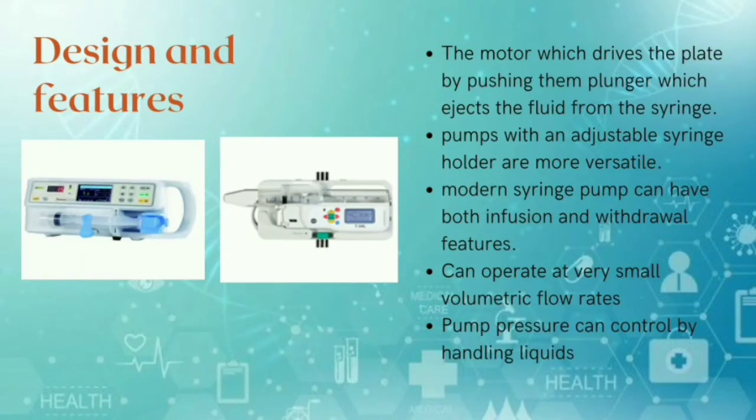Now, let's move to the design and features part of the device. It has a motor which drives the plate by pushing the plunger which ejects the fluid from the syringe. We can use two syringes to achieve continual flow, where one pulls liquid and the other pushes the liquid. Pumps with an adjustable syringe holder are more versatile in their applications.